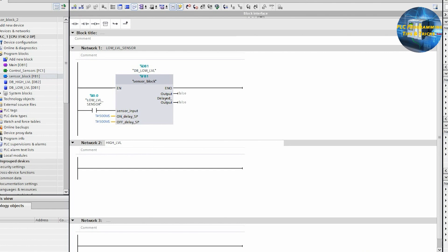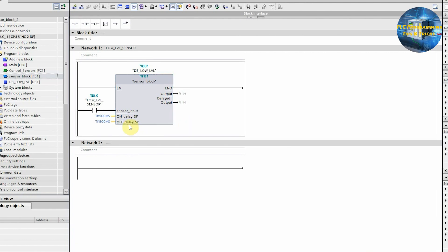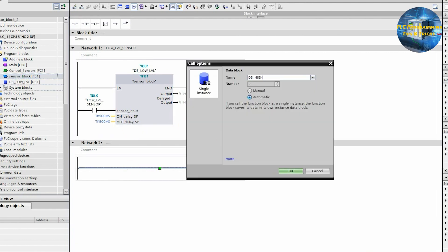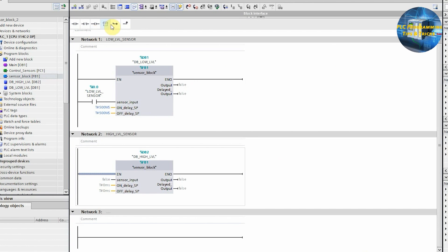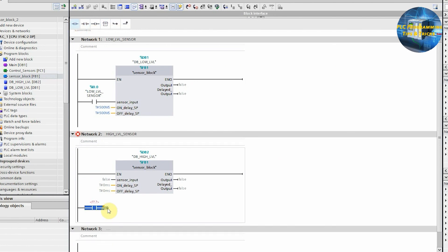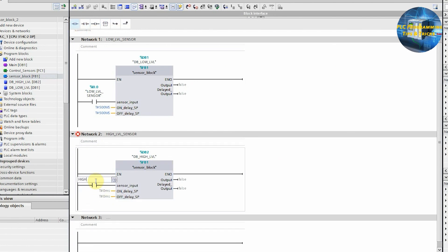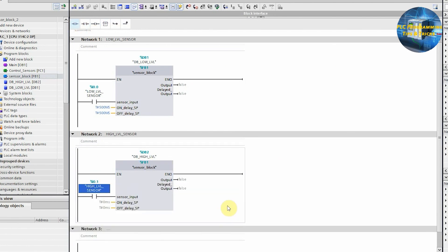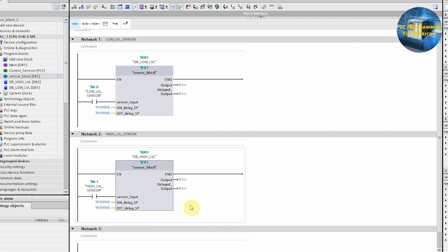Next, in network number two, we will create an instance of the sensor block for the high level sensor, as we have done earlier. We will assign the I0.1 input of the PLC at the sensor input of the block. I0.1 is the high level input of the PLC. Next, we will set the on delay and off delay time as 500 milliseconds for this block.